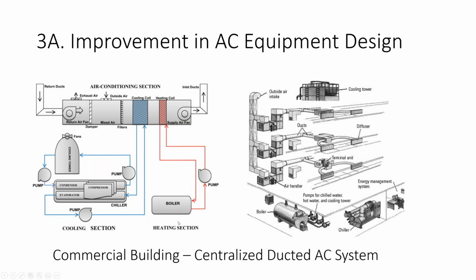And for the heating system, we have a boiler that does the same thing, but the heating system is not part of our discussion here. On the right side, there is a distribution system. In this diagram, it's a three-story building, which we have divided into three zones, and every zone has its own air handling unit. You can see that there are three air handling units. If it is a 10 or 20 story building, that number could go higher as well. I believe I have explained all the components. On the distribution side, you can see that we use air handling units, ducts, diffusers, piping, and ductwork. Those are all the components of the air handling and air conditioning system that I'm going to talk about in terms of efficiency.